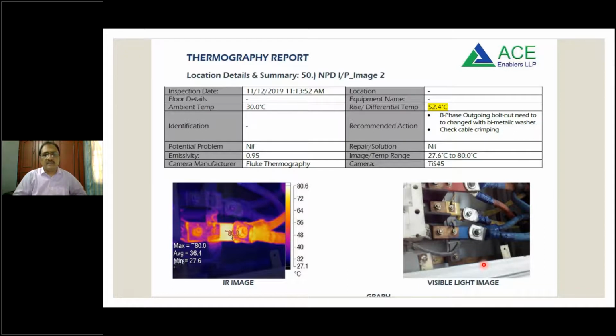One slide, I think, on the thermography. This is an important tool which is now added to most of the energy auditing people's repertoire. The reason is that normally you will not see the difference in temperature. As you can see here, through the thermal vision, we found that the average of the three phases put together was only 36 degrees centigrade, whereas one phase, which is I think the blue phase or yellow phase, showed 80 degrees. This is possibly because of a loose connection or because of not using a bimetal washer. So we'll have to find out why it is happening and then immediately rectify it before it becomes dangerous.